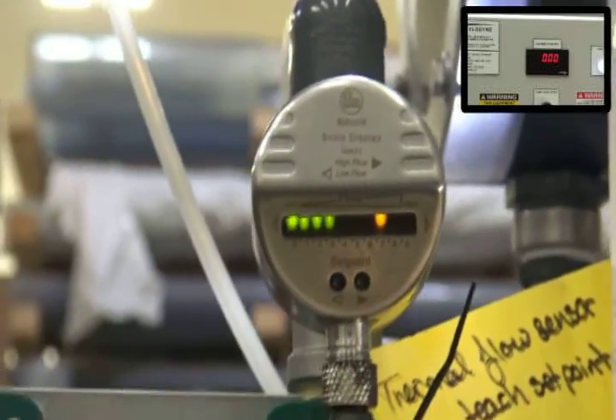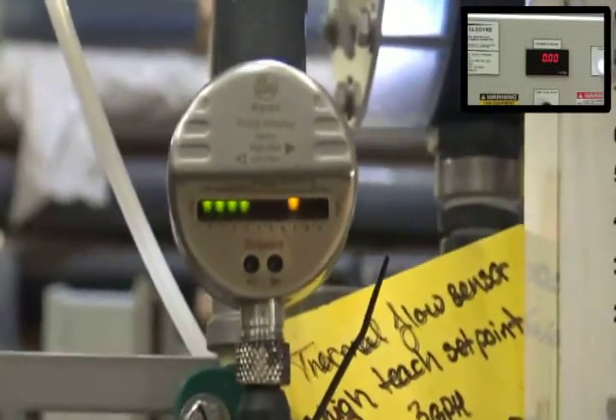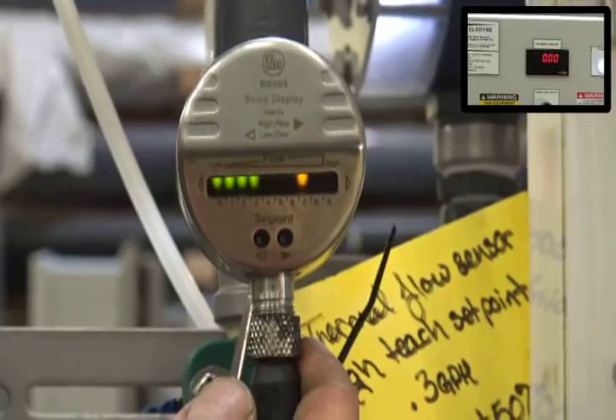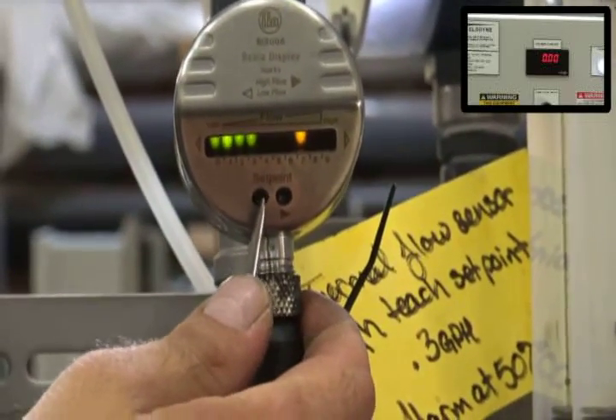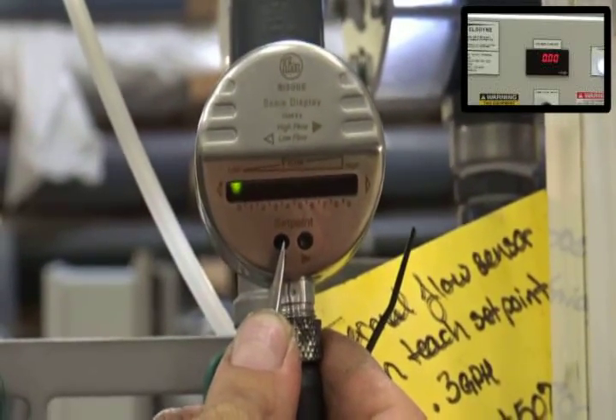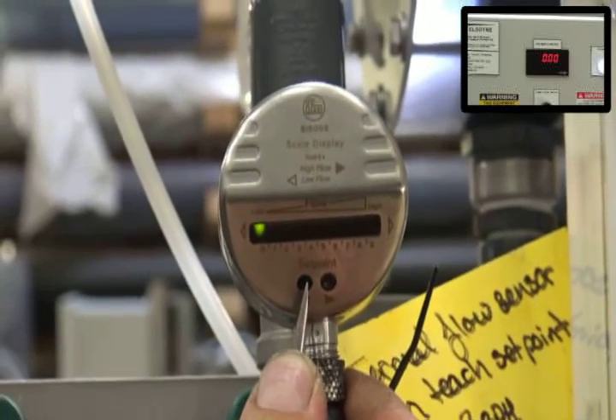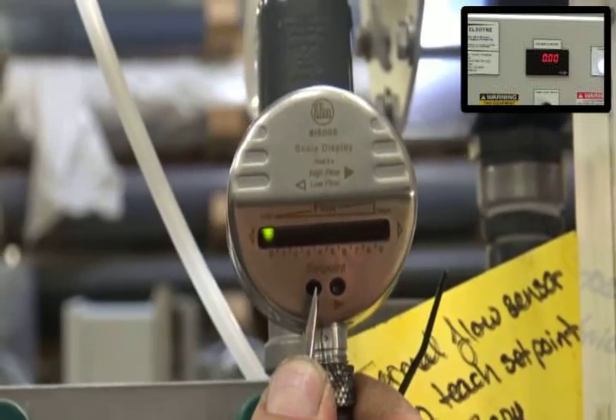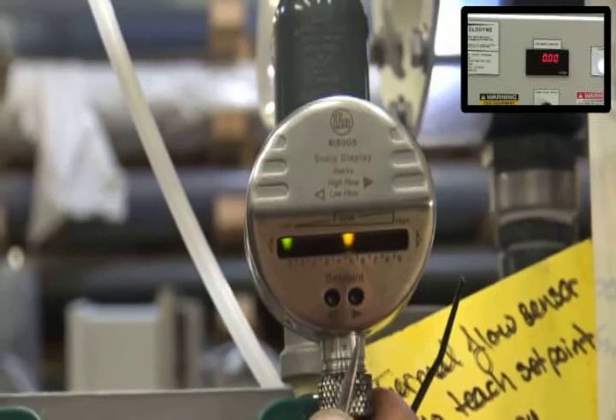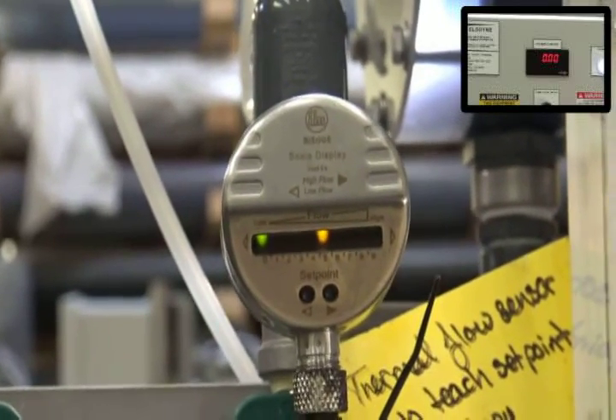So we've let it run for a while, and it's pretty much stopped going down, so now it's settled out. So we're going to do a low teach. We're going to hold the other opposite button. Green light turns solid, it'll start flashing. Once it starts flashing, you let go, and it's done the low teach set point.